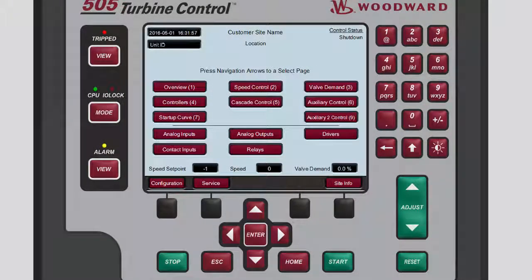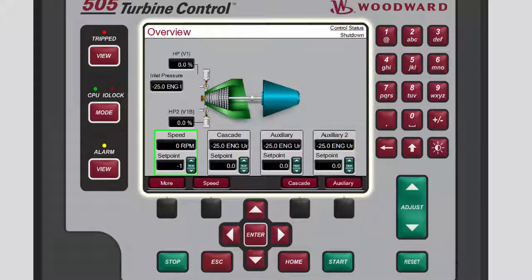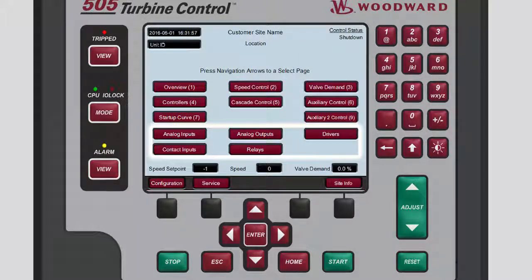They can be navigational or operational. Once configured, the 505 boots up to the home screen. The buttons displayed on this main screen vary depending on the functionality you configured for your particular 505. The buttons on the home screen are divided into two categories: Run Operation and Input Output. The Run Operation buttons are located on the top half of the screen. These buttons allow you to access screens pertaining to running and operating the turbine. For example, the Overview screen shows a summary of configured controllers. The Input Output buttons are located on the bottom half of the screen. These buttons allow you to access screens that display the status for all available channels for the different types of inputs and outputs.